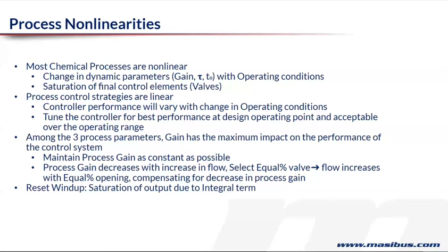So you are not looking at a third decimal point, neither a second, neither a first decimal point. In fact, it is such an approximate method that when you change the gain or the integral, you change it by twice the value if you are increasing, or reduce it by half if you are decreasing. Increasing by 5% and so on, you will not even see any change in the process. Out of these three parameters, the gain has the maximum impact on the control system.